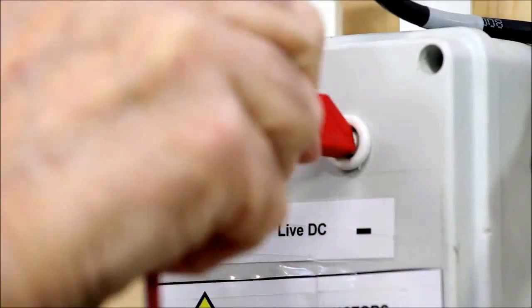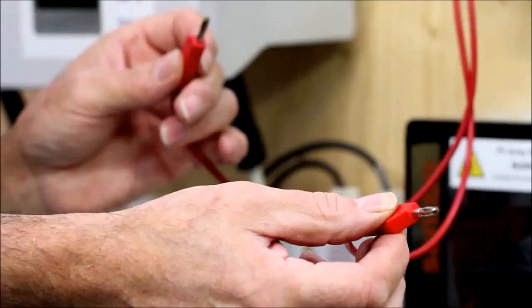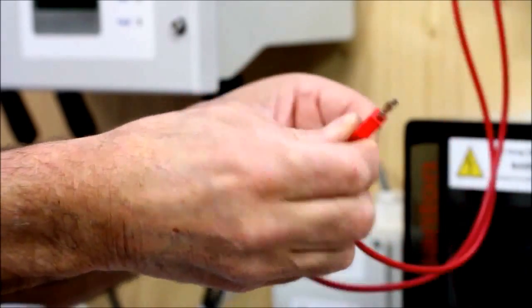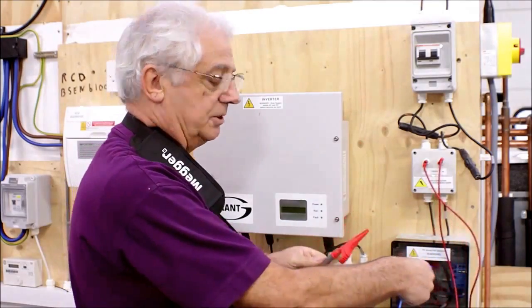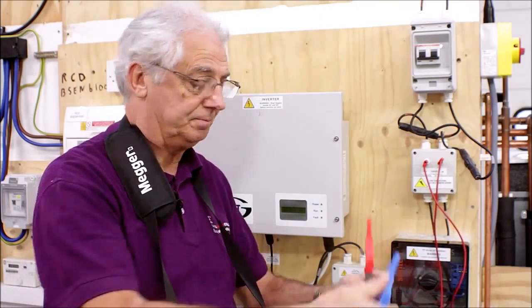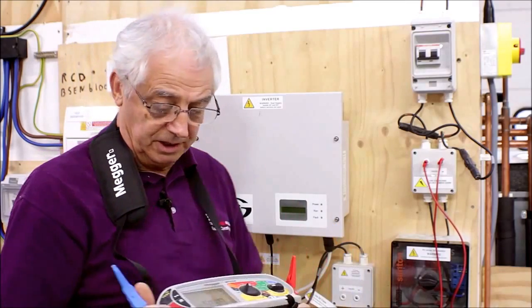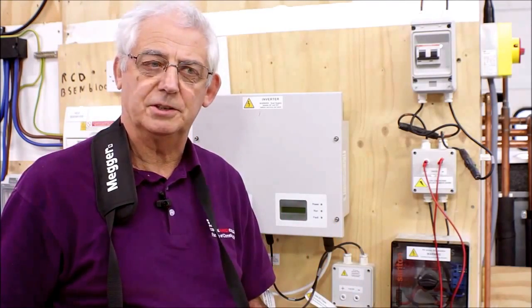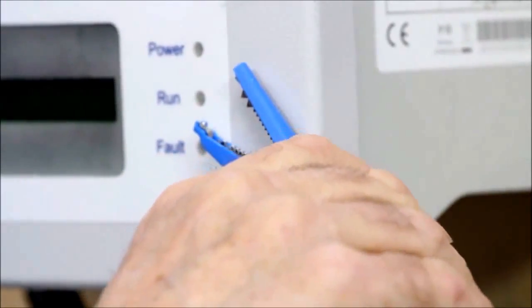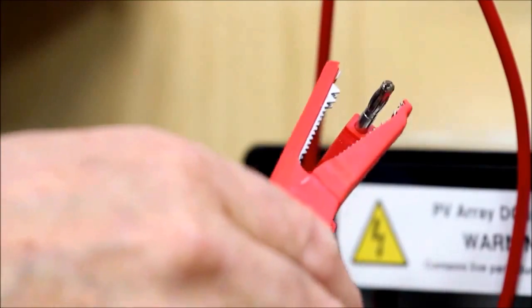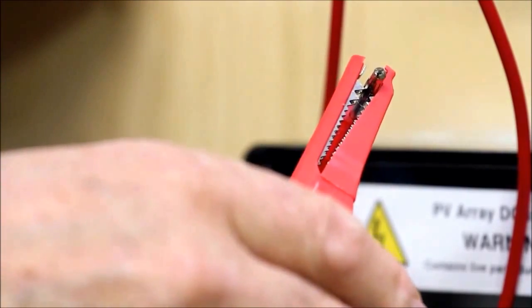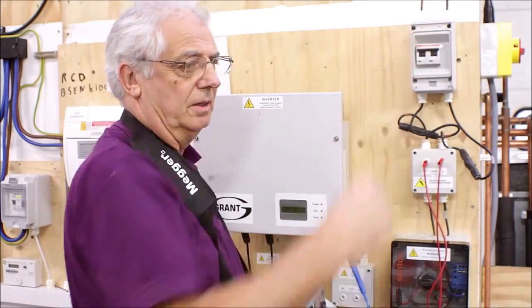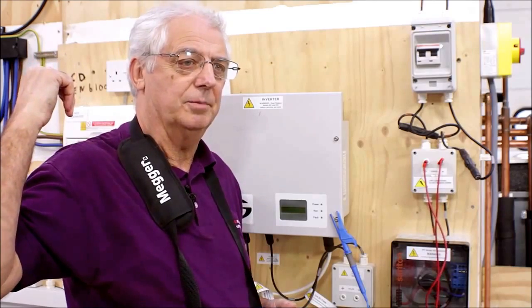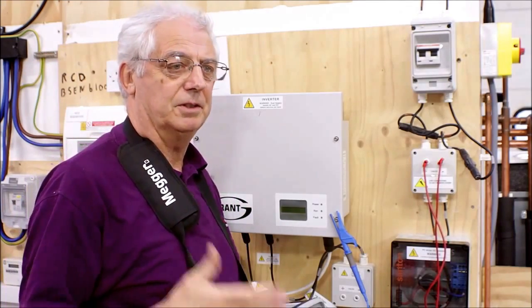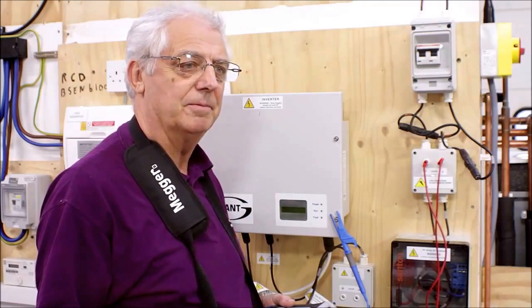Then I use two leads which I've got and join them together. Now, of course, what you could do is you could use a probe and test your line and your negative conductor separately. This just saves me a little bit of time. The instrument's set to insulation resistance. I connect one probe to a known earth and the other probe to the contacts that are joined together. When I turn this on, of course what I've done is created a short circuit at the PV panels, but that's going to do no harm because they can't generate more than they're made to generate.